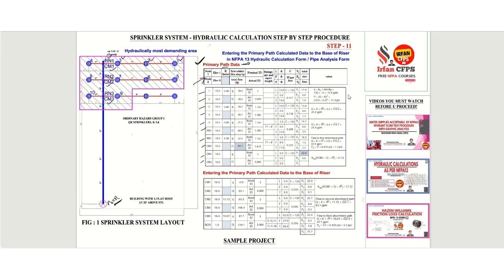Since we already discussed how to enter this data, I'll go through this step thoroughly. The elevation is 19 feet for both Node 1 and Node 2 — that's a print mistake. The K-factor at Node 1 is 5.6, and Q will be 18.9 GPM using the area times density formula shown on the right side of your screen. We are considering a 1-inch pipe, and the length between Node 1 and 2 is 14 feet.